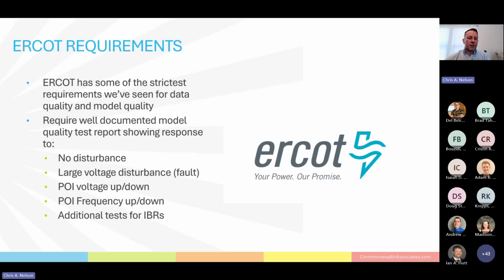So just to cover some of the specific utilities we've worked with and seen: one of the strictest ones we've actually worked with is ERCOT. Probably because they're a smaller grid, they have to have more quality control just to make sure they function. They have a lot more strict requirements for model quality and model testing than anybody else we've seen. They have a specific form you have to fill out, and you have to run different faults on the site depending on whether it's an inverter or conventional generation. They have very specific tests you have to do, like requiring the point of interconnection to be at a certain voltage or frequency and seeing what your generator does. If it doesn't reach this exact level, it fails the test.